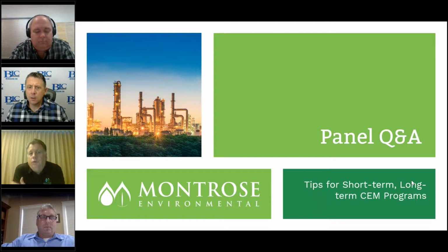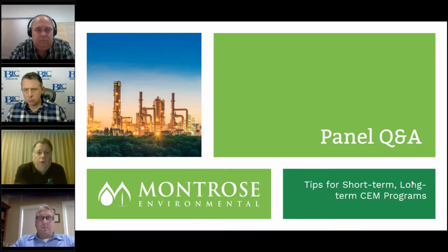That's a good question, and the hurricanes add another spin to it. We generally try to avoid running temporary CEMS off of generators if we can. For short-term applications they work, however generator power is generally not very stable, and as the power fluctuates it could affect our analyzer readings. So shore power is always preferred.